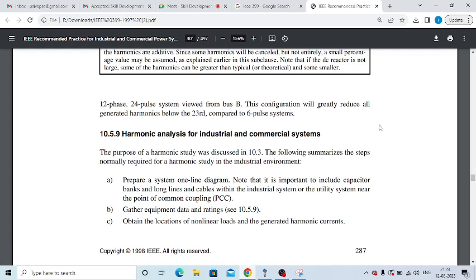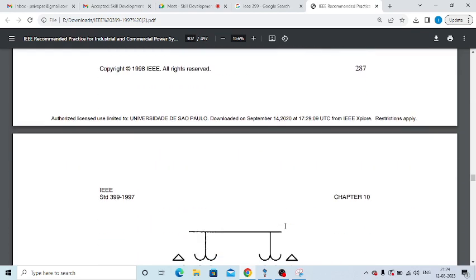In a single line diagram, we see where all the non-linear loads are coming, and what non-linear current a particular load can generate. Suppose 10 non-linear loads are there, and all 10 loads have different ratings. We have to get the harmonic current generation of all 10 loads. What harmonic frequencies can it generate, and what is its magnitude and phase angle? We have to get this information from the particular non-linear load manufacturer. Suppose it is a VFD manufactured by Siemens, we have to get it from Siemens. If it is from ABB, then we have to get it from ABB, right?